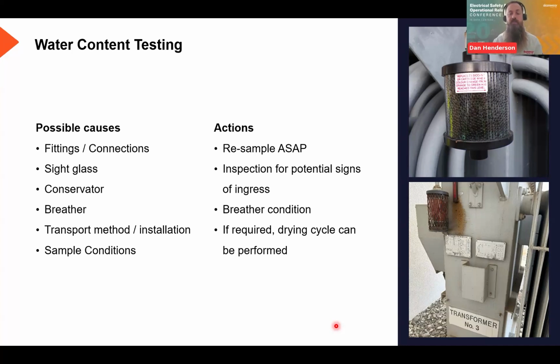We will come back to this to understand. You do have to have further information, because if some of the other conditions of the transformer aren't correct, when you're doing this process of recirculating the oil, you can actually cause more damage as well. So an example that I've experienced is where there was an increased parts per million, and the more that this was done, which the client insisted on, recirculating the oil, ultimately it was just degrading the paper insulation on the winding. So it's just important to be mindful of that.